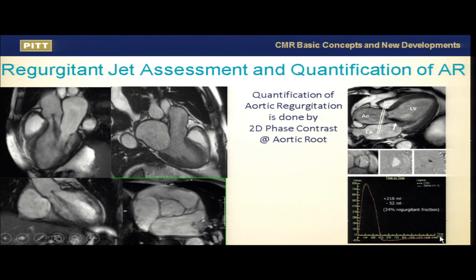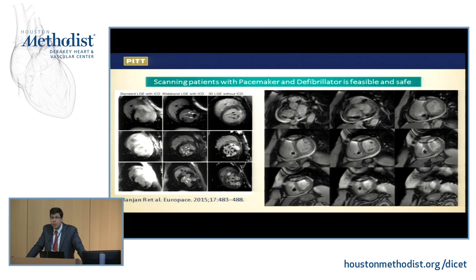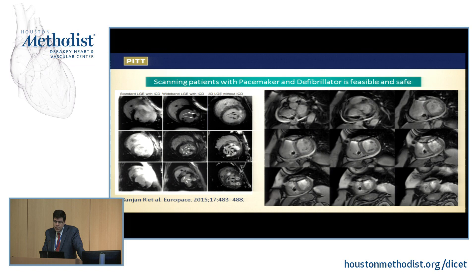Here are some new developments coming into daily practice. Scanning patients with pacemakers and defibrillators is now possible. This patient came to our lab about a month ago with an MRI-compatible ICD device. As we can see, there is artifact from field inhomogeneity created by the generator, which produced artifact on the right side.